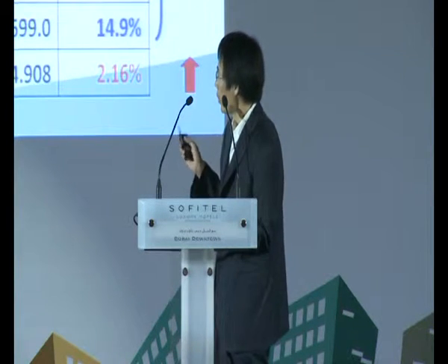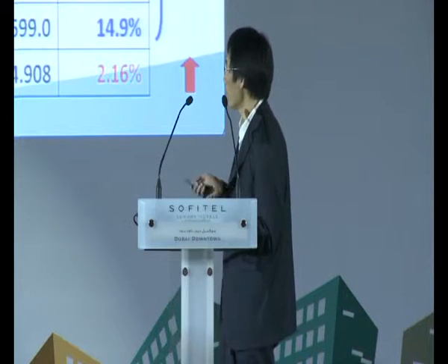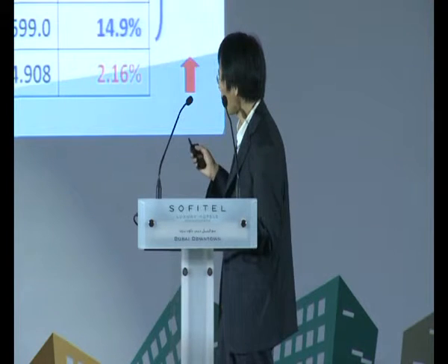Lifetime and reliability, which is a favorable feature for the R290 to be used in the high ambient temperature region. So compared to the R22, R290 has lower cooling capacity, but it has a higher COP.